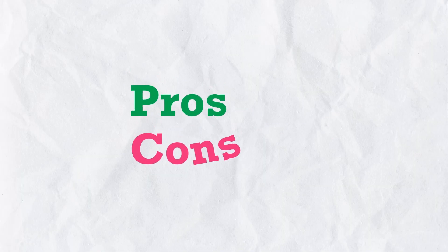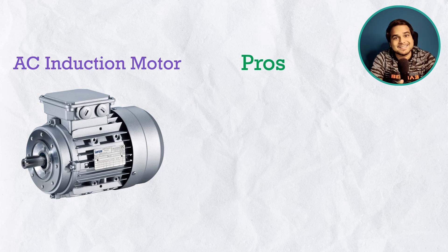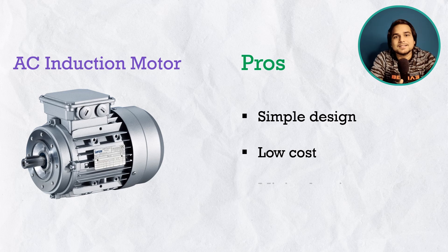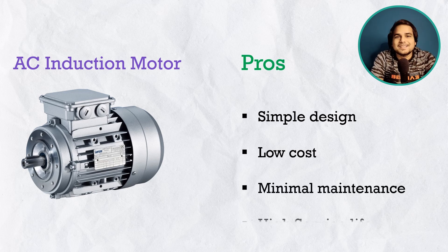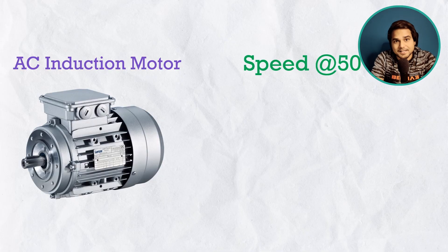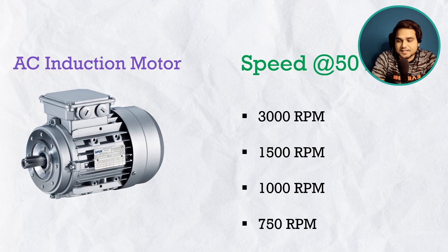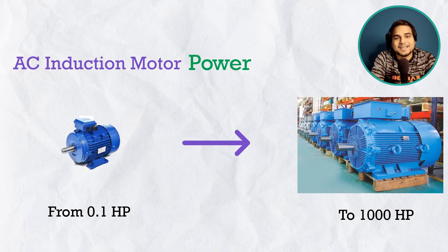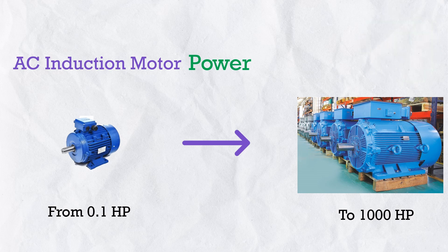The pros of the induction motor include its simple design, which keeps cost low and maintenance minimal, with a longer lifespan than most other motors. At 50 Hz, available speeds are 3000 RPM, 1500 RPM, 1000 RPM, and 750 RPM depending on the number of poles. Power range spans from a quarter HP to thousands of HP. However, rated torque is only available at rated speed.